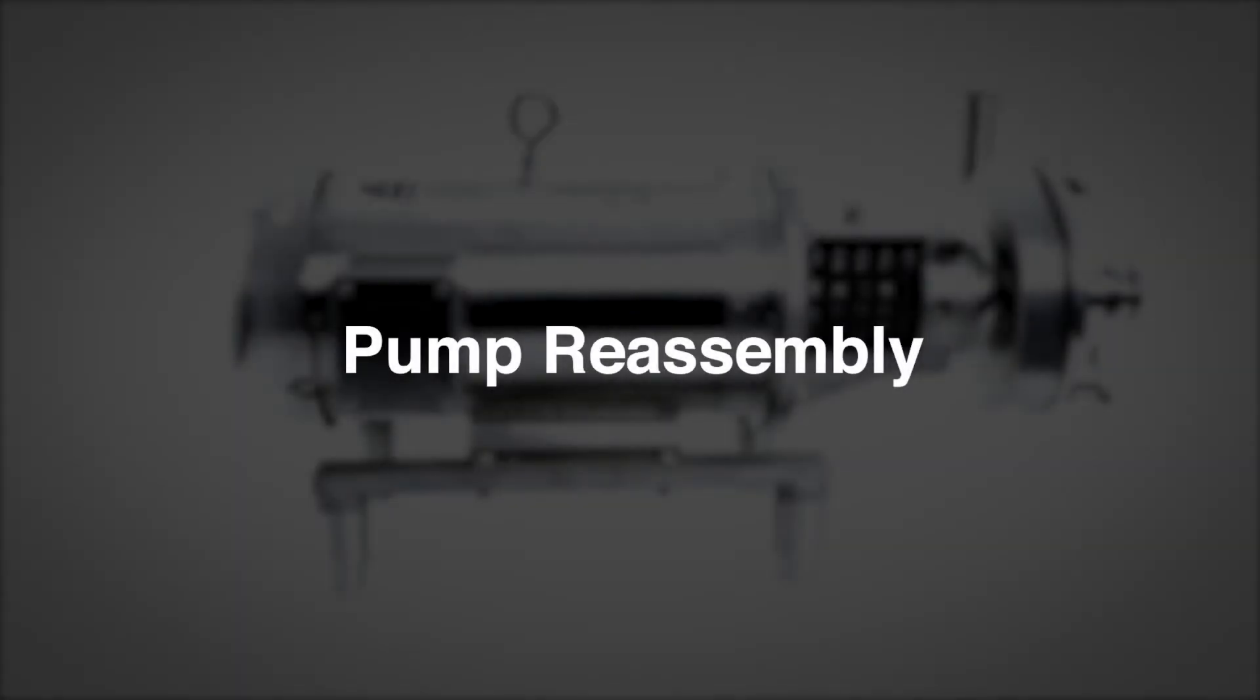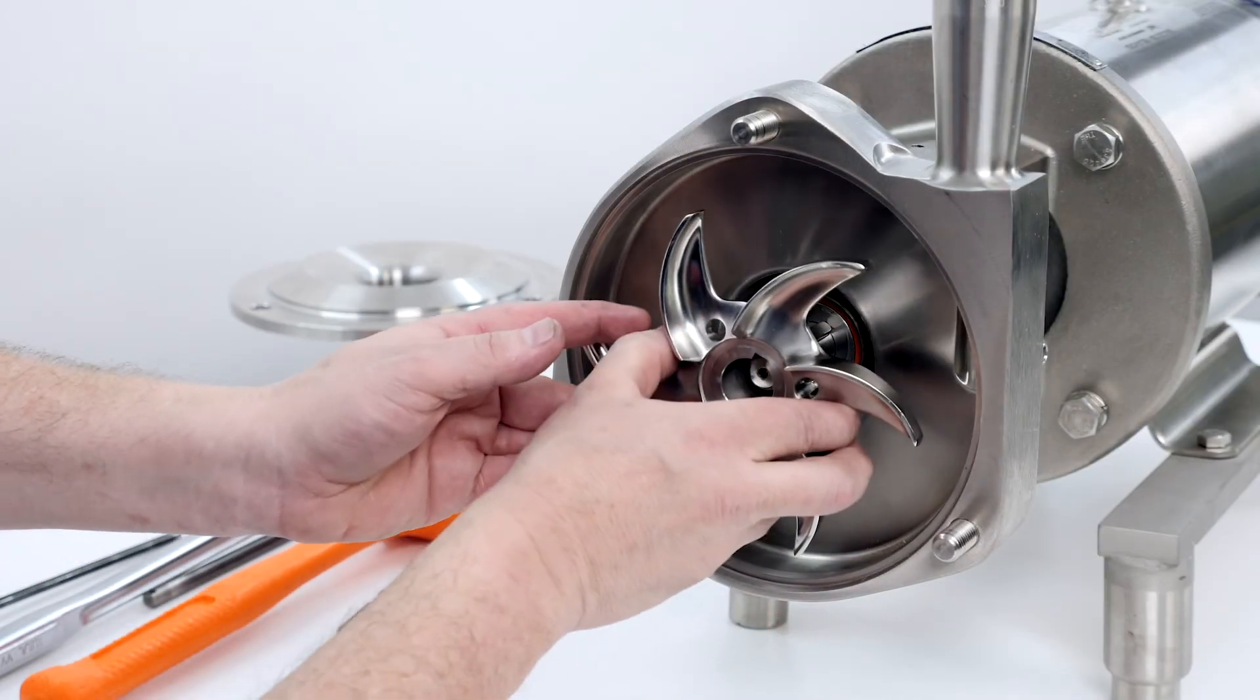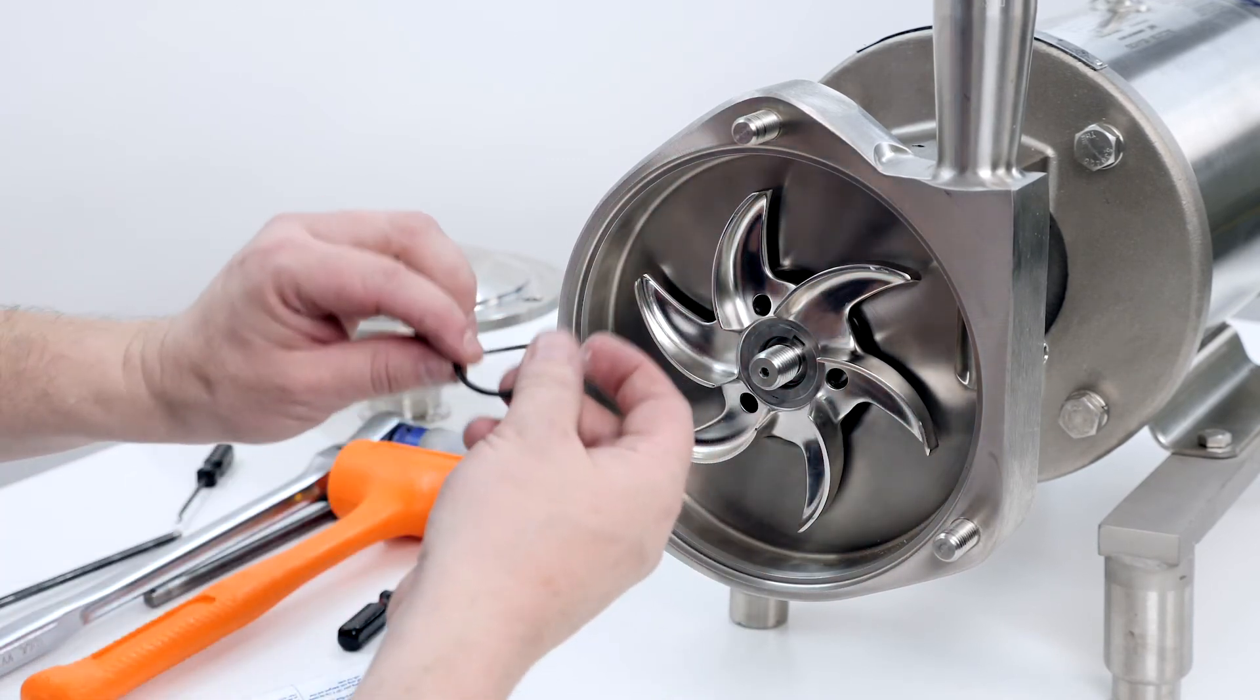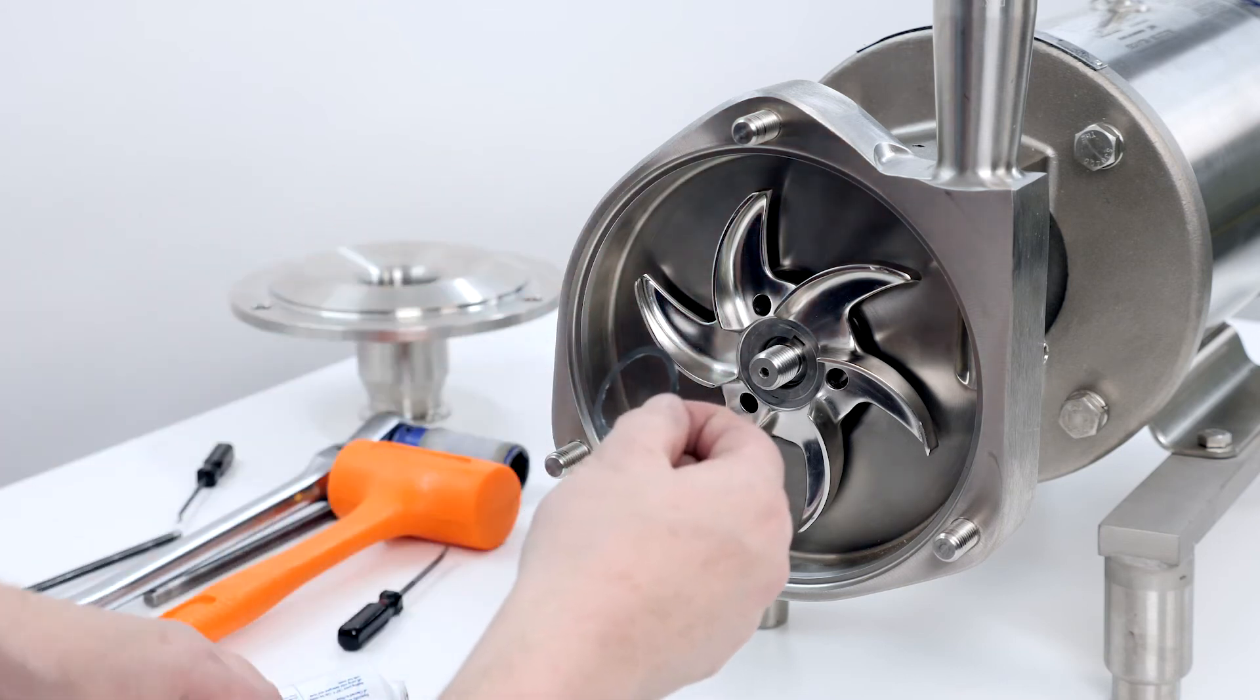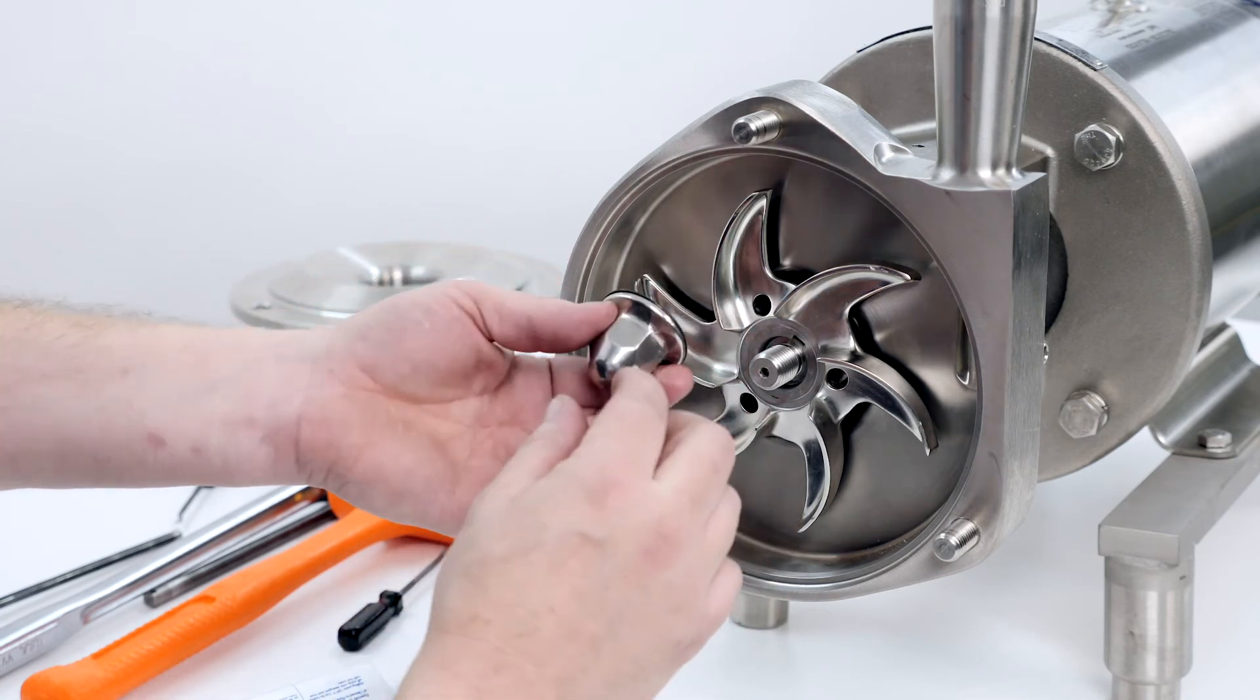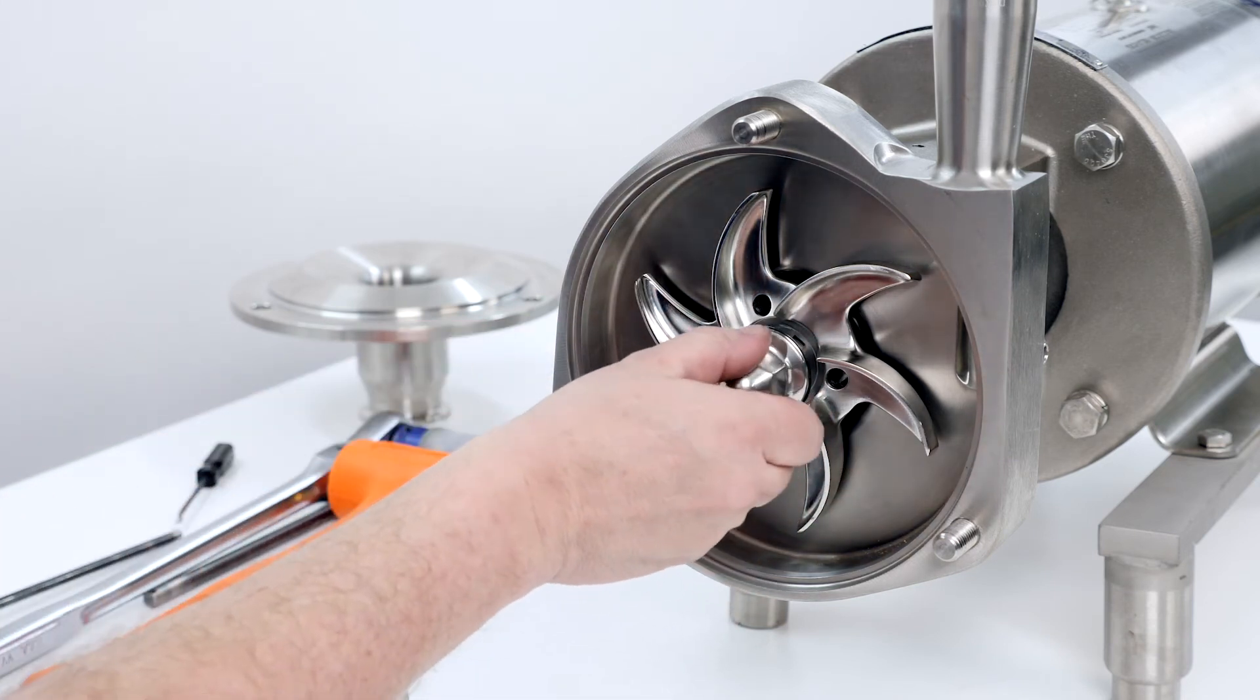Pump reassembly. Slide the impeller onto the shaft, making sure to align the keyway in the impeller with the key in the shaft. Lubricate the impeller nut gasket and place it onto the impeller nut. Thread the impeller nut onto the shaft.